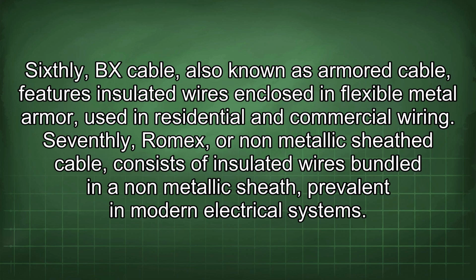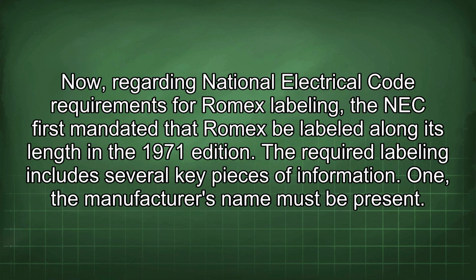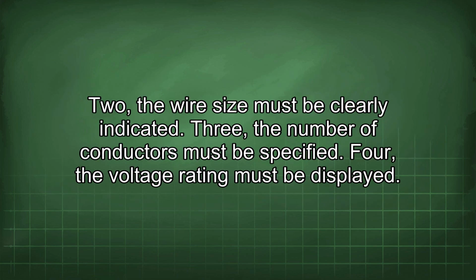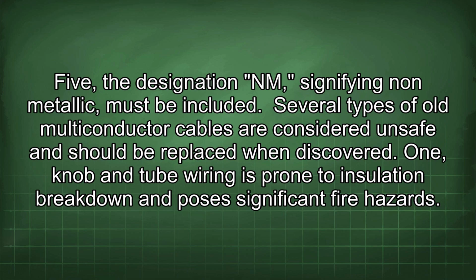electrical systems. Now, regarding National Electrical Code requirements for Romex labeling, the NEC first mandated that Romex be labeled along its length in the 1971 edition. The required labeling includes several key pieces of information. 1. The manufacturer's name must be present. 2. The wire size must be clearly indicated. 3. The number of conductors must be specified. 4. The voltage rating must be displayed. 5. The designation NM signifying non-metallic must be included.